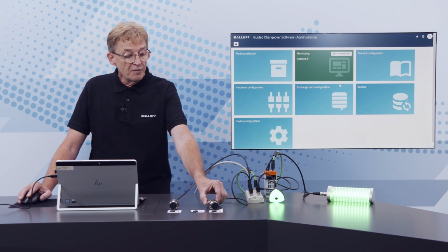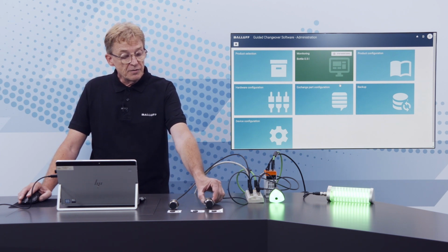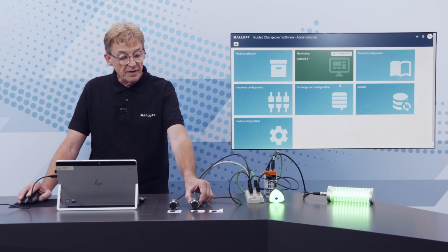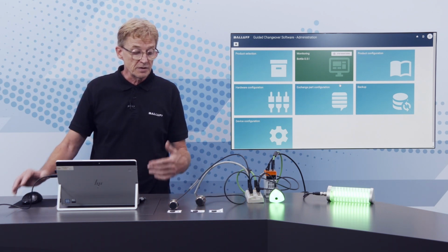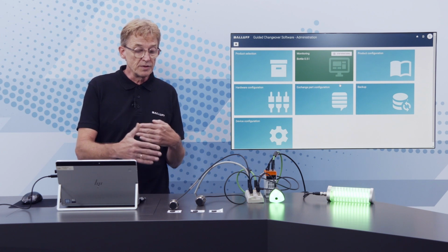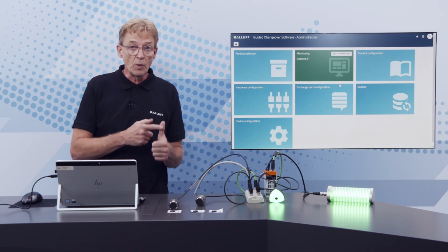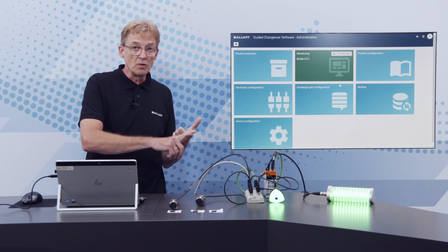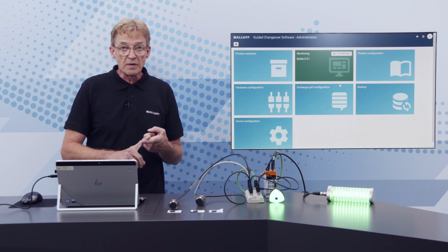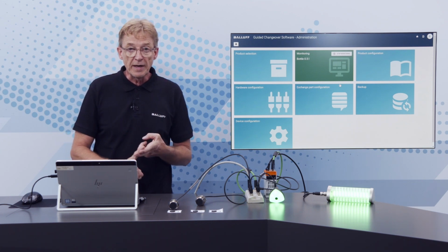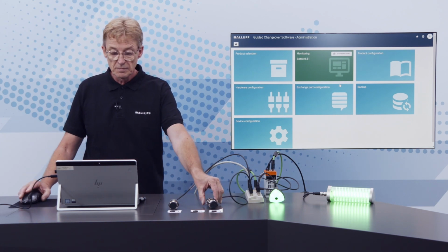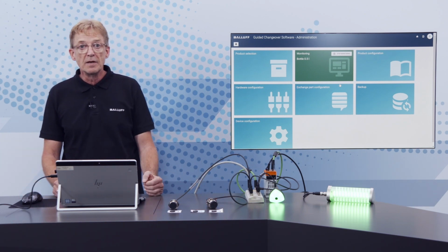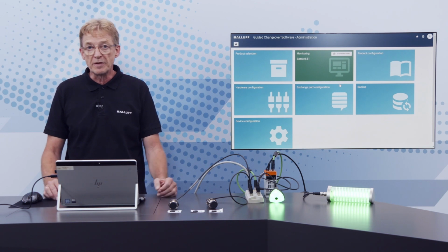And if we move the RFID read-write head back from the other tags, you see that nothing will happen because this is a single detection. It's only necessary to read in these tags one time and then use the tools in the application, and you are not getting any error if you don't see the tag anymore. That is the difference between the single detection and the permanent detection.